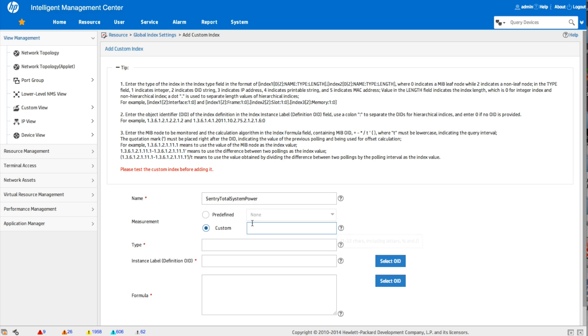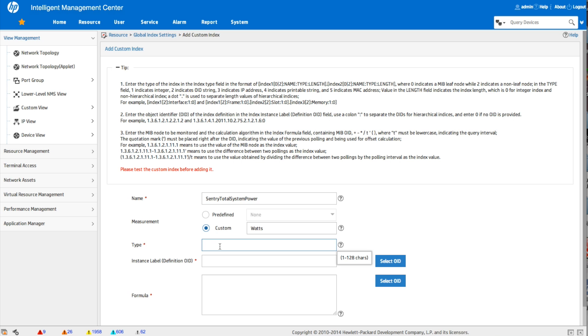So next we're going to go and actually define the measurement type. So that's going to be watts here. So you might want to look at the predefined to see if there's something there, but I happen to know watts is not one of them. So for this next step, this is a little bit trickier. You might want to look at the administrator guide to get more familiar with this as well. There's some tips up here at the top. I've already figured this out. So we're going to go index one bracket, zero bracket, colon, and we're going to put a label in here now. So this is usually what I tend to do is the label of the actual MIB. So system total power was the name of that, the English descriptive name, colon one, colon zero, close it off. There we go.